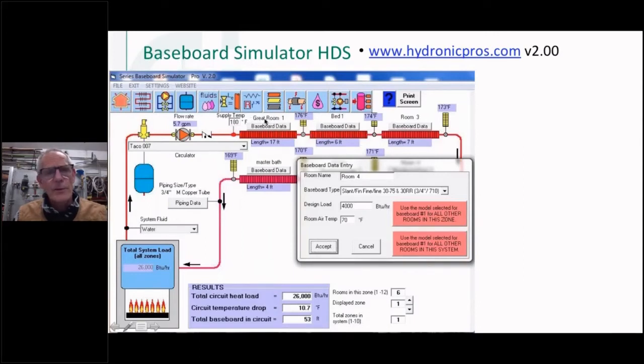So if I put in this great room, I think I might have had a 10,000 BTU load in there. It'll tell me the length of baseboard I need to cover that load in that room under this condition. What I like about this is every time you go to the next room, since I'm in a series here, it's going to tell me what the available temperature is at that next baseboard. So what I did on these bedrooms here is I put the same load on every bedroom. I call them the guest bedrooms or the kids' bedrooms.